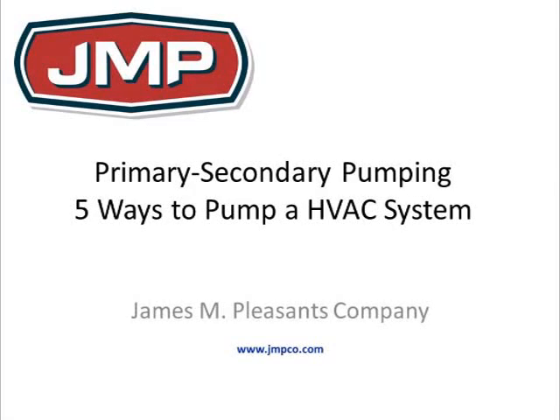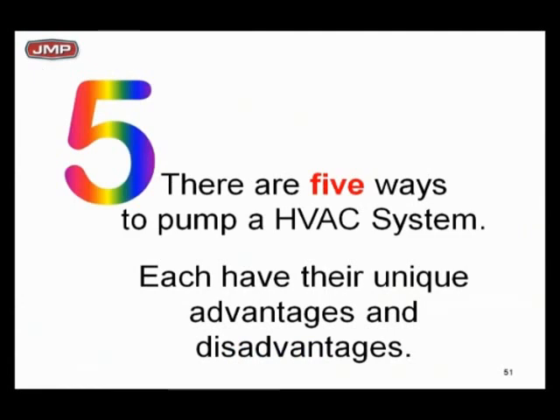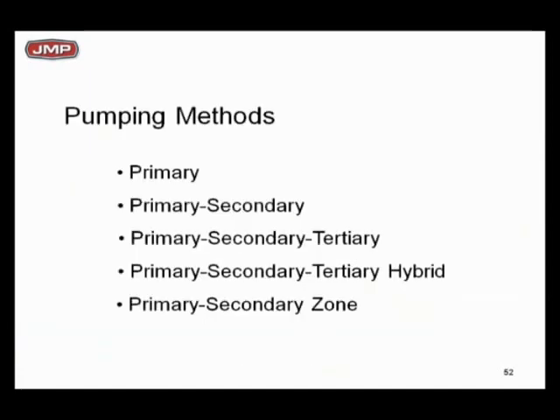It's important you understand that you cannot design a building today without primary-secondary in some form or fashion. Looking at the building blocks you need to understand — of which primary-secondary is a big piece — when you design a chilled water system, hot water heating system, a chilled water plant, a hot water plant, or central plant, you're going to be using one of these building blocks or a combination: primary pumping, primary-secondary pumping, primary-secondary-tertiary, primary-secondary hybrid, or primary-secondary zone.